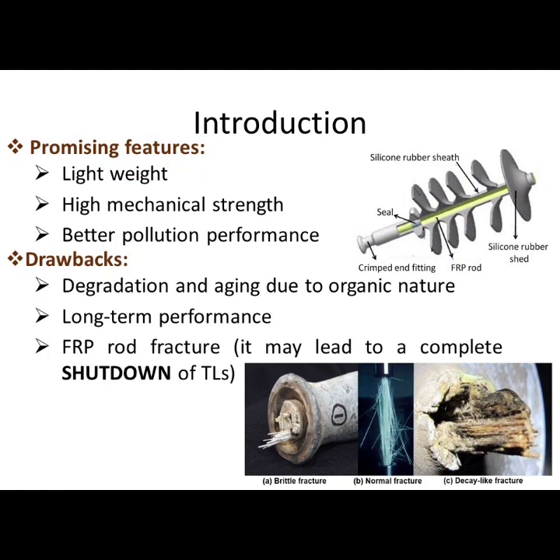So there are two types of FRP rod fracture which are well known: the normal fracture due to a higher mechanical stress than the rated value, or the brittle fracture, which is due to the stress corrosion crack of the glass fiber. However, a new type of FRP rod fracture has been reported in many countries, known as decay-like fracture. This new type of fracture is mainly due to the degradation of the epoxy resin matrix under the action of electrical discharges and also due to water and acid penetration through the silicone rubber housing.